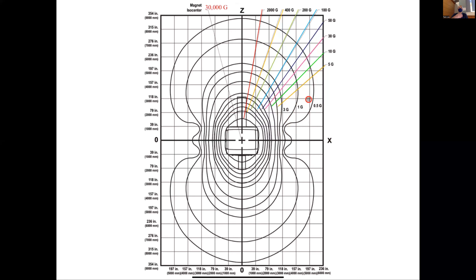Okay, so where is that here? Half a Gauss. According to safety regulations, you have to keep this half Gauss line within the magnet room. This half Gauss line cannot go outside. The reason for that is not totally clear, and it's probably too conservative. But for the older generation of pacemakers, the concern was that there are quite a few people who come to a hospital with pacemakers. If they walk past an MRI room and the field is too strong, it causes electrical currents in their pacemaker, which can screw up their pacemaking. That was the main concern.